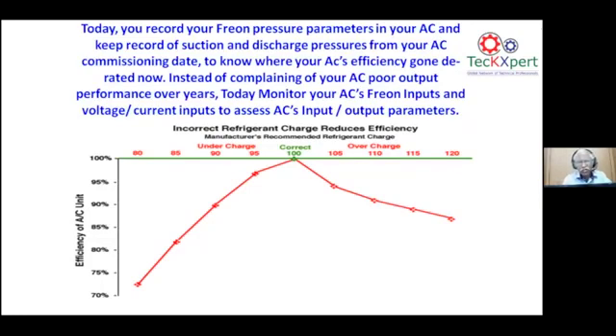I am just telling you on a case study. Normally the pressure is around 70 psi. You can have a pressure gauge with an alarm. If it goes below 50, it can give you an alarm. If it goes above 280 psi at the delivery of the condenser, you can have an alarm. These are all the areas where the alarms will prompt the user to correct the problem before it happens, not allowing the Freon to escape or to choke the condenser and cause a problem.